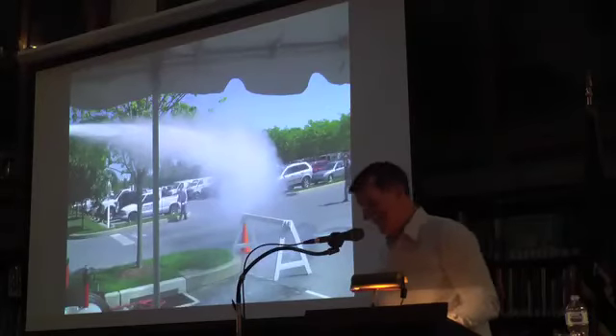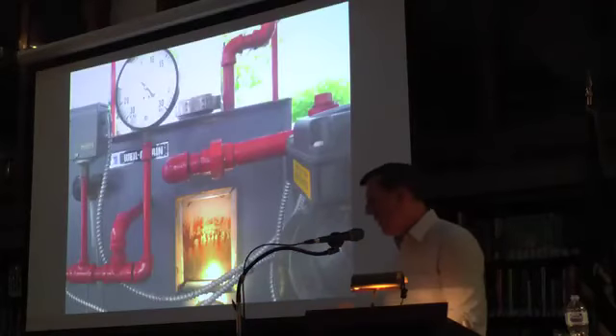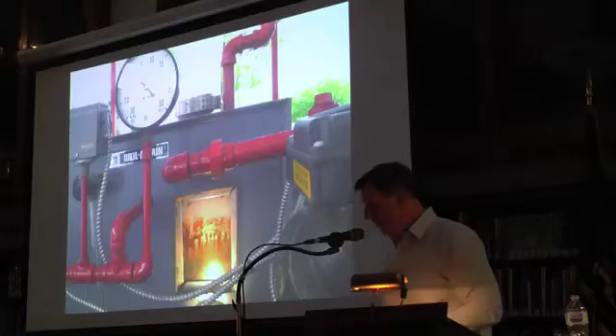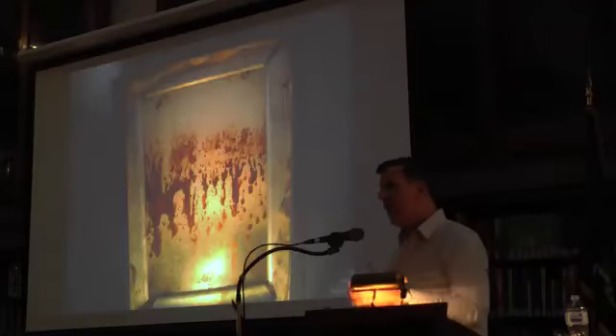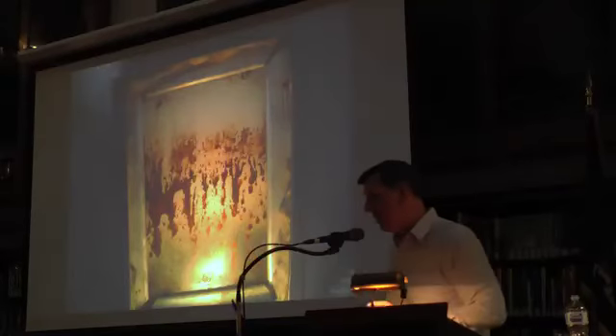Stop texting, right? So all the while this is going on, when we look at this boiler, if you looked at the gauge glass, it's barely moving. It's moving maybe 1/4 of an inch up and down. But when you look inside the boiler, it looks like a washing machine in there. It's going crazy. So what's going on in your gauge glass is not what's going on inside the boiler. And you got to make sure you get both of these things straight.